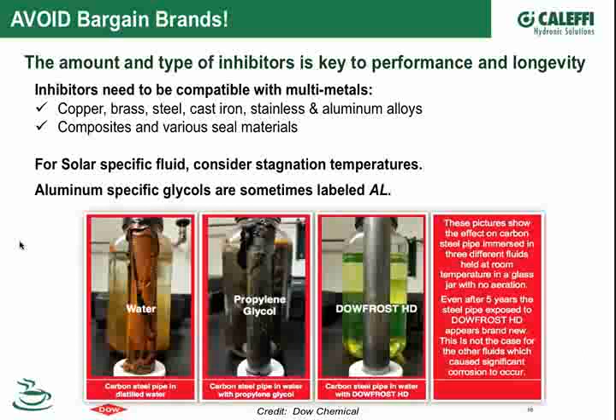Then you see the one with our Dowfrost HD, carbon steel looks brand new, and that's 5 years in, as it explains in that slide. So it is possible to have formulated products that provide the corrosion protection you need. You just need to make sure you get the product that meets your system needs.